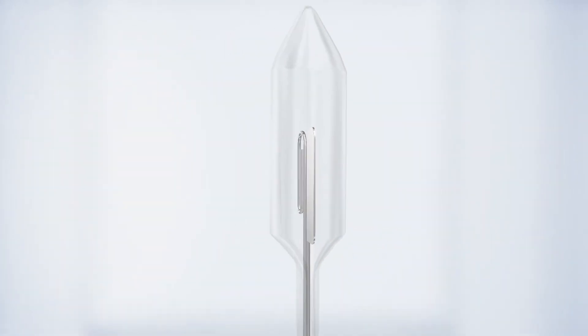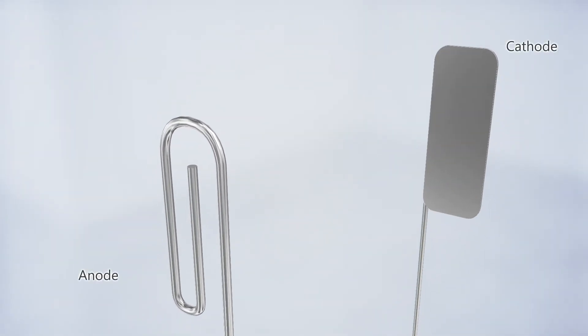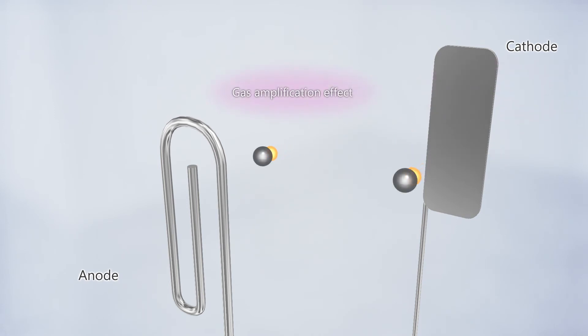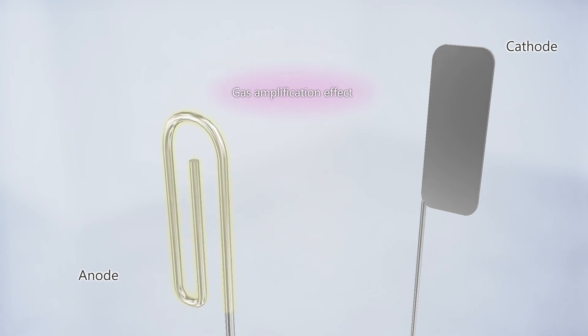Let's take a brief look at the operating principle of UVtron. When UV light passing through the UV glass strikes the cathode, the cathode emits photoelectrons. These photoelectrons are drawn to the anode and collide with gas molecules which become ionized. The electrons then reach the anode while repeatedly colliding with other gas molecules which also become ionized. By utilizing this gas amplification effect, the current is amplified and extracted as an electrical signal.